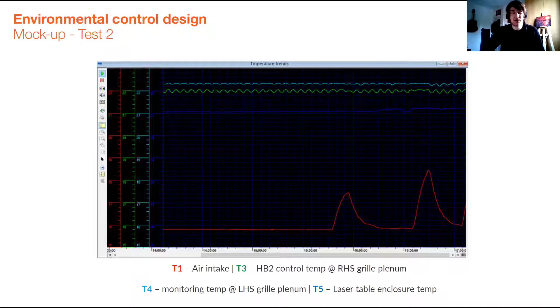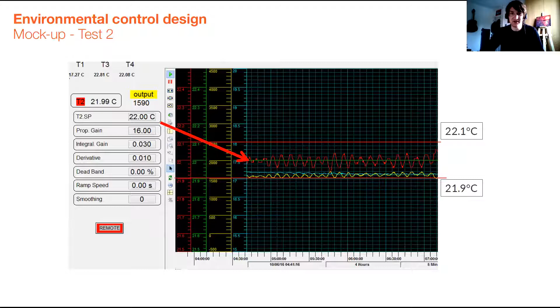Effectively, we were able to achieve the temperature control we required, plus or minus 0.1, with the system following those modifications. It was a real success story, and it was brilliant that we'd done that on a mock-up, because it meant we could feed those lessons we learned into the design.